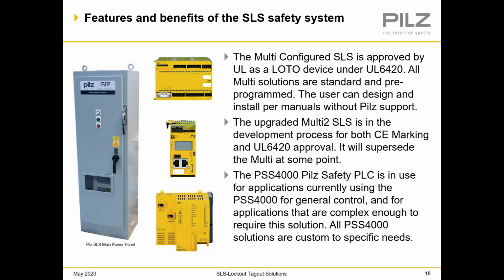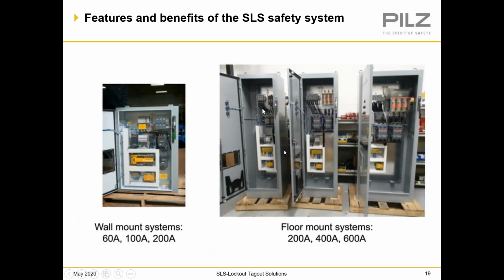And the other application for PSS 4000 is if you have a fairly complex requirement where you have, like I said, a lot of multiple remote station requirements, but you also have multiple sources of power within a particular cell, then the PSS 4000 might be a better way to go because of its capability and larger I/O structure within that. But all PSS 4000 solutions are custom designed for specific needs.